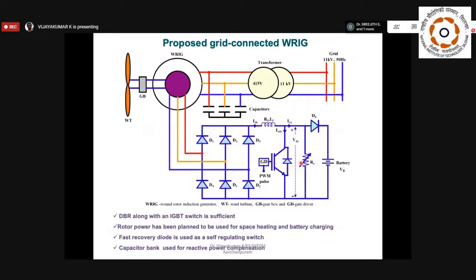So what we have proposed is, earlier they used the fixed resistance, so all the slip power is wasted in the resistance itself. Instead of wasting the energy in the fixed resistance, we can use it for space heating applications. Normally wind turbines are located in remote areas. You can think of it because here they may use a 1 megawatt turbine. So 30% means it's almost 200, 300 kilowatt.